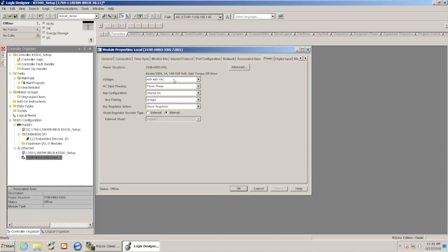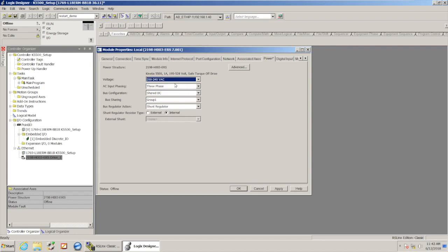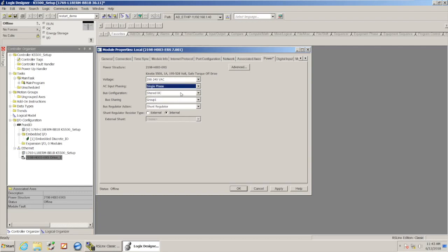If you have 480-volt three-phase that you're running to your drives, you'd leave these settings as they show for that part. In this case, I'm going to set mine to 240 volts AC, and I'm going to set the phasing to single-phase.